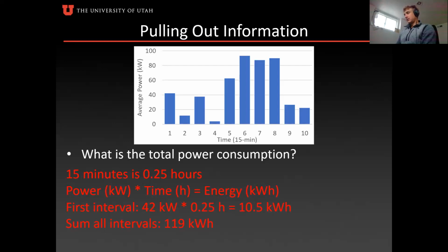And we caught it too late. We'd already turned in the assessment, but that would definitely be something good to check if you have this interval data, right? Check to make sure the monthly highest average is what they're being charged for. And if it isn't, we should check with the utility to see if they need to recalibrate their meter or whatever they need to do. But it'd be interesting to check that.